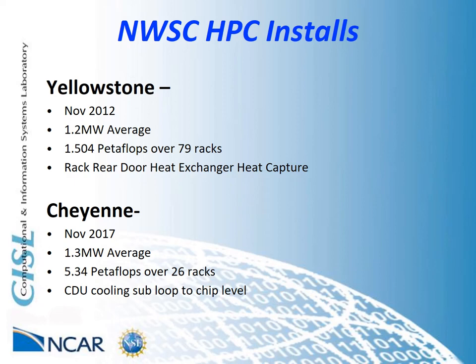The average power draw for this system is roughly the same as Yellowstone at 1.3 megawatts, but the performance was increased to 5.34 petaflops. The total footprint for this system was also dropped by a third, for a total of 26 racks. The HPC system was cooled by a CDU, cooling distribution unit, with a cooling subloop. The system performed heat capture at the chip level for a majority of the system.